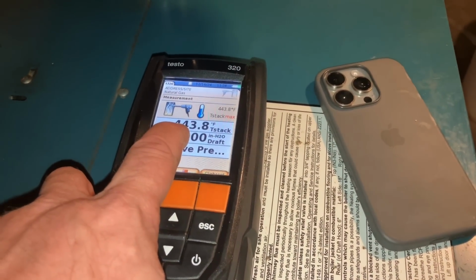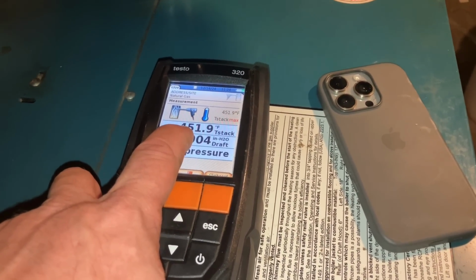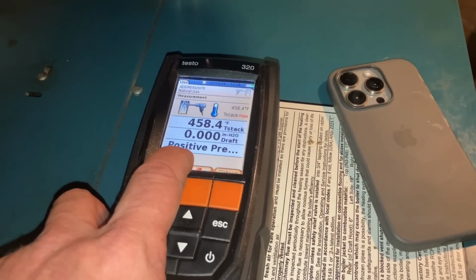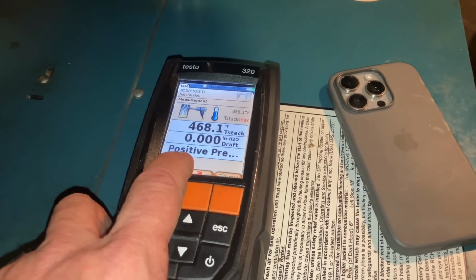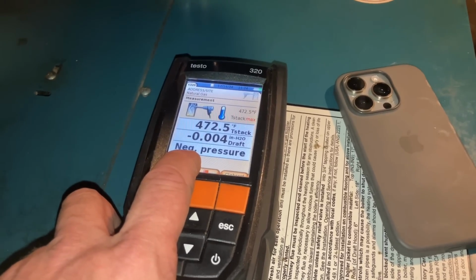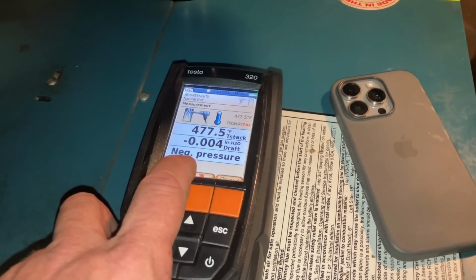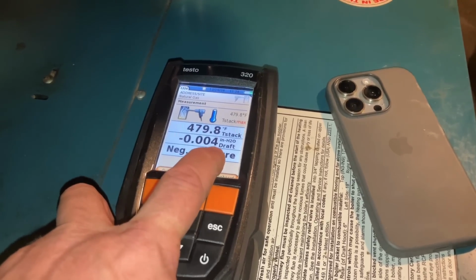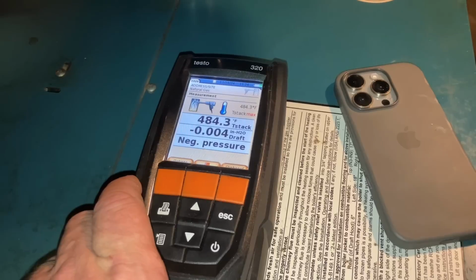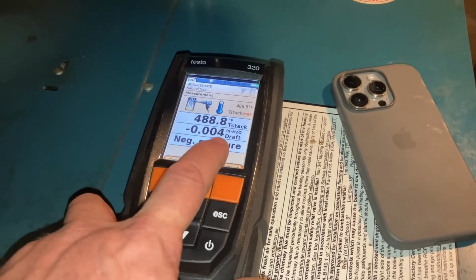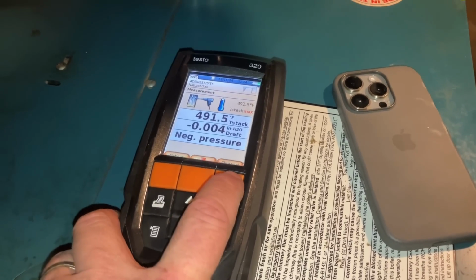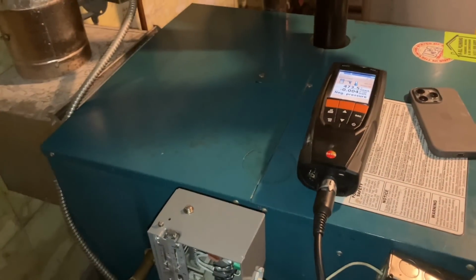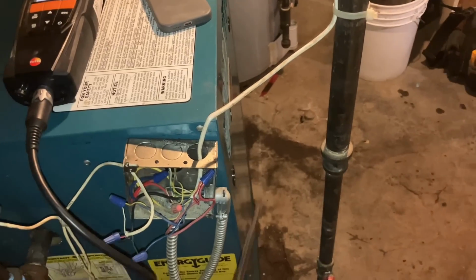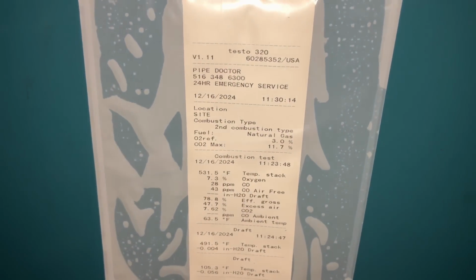This will approach our number during the combustion test, and we're going to make sure we have negative draft. Right now it's positive with 0. There we go, negative with 4 thousandths negative inches of water column here. Still climbing, still negative. That's good. We're going to clipboard that as well. Take our probe out and then print the results to document and put a copy in front of the boiler. All right, there's our combustion and draft analysis results.